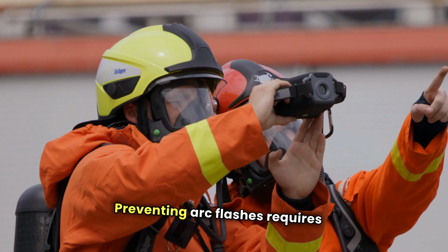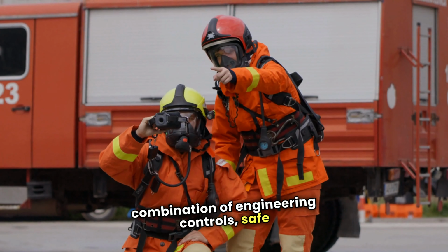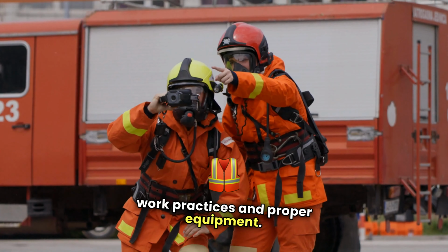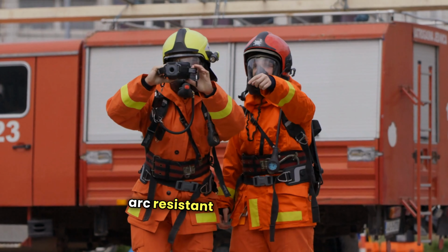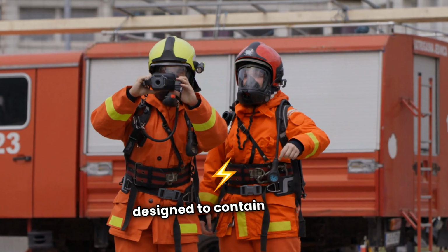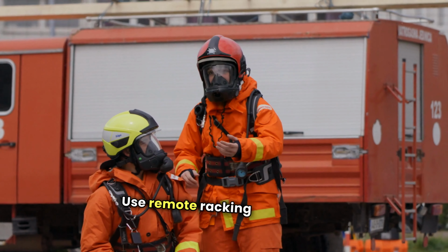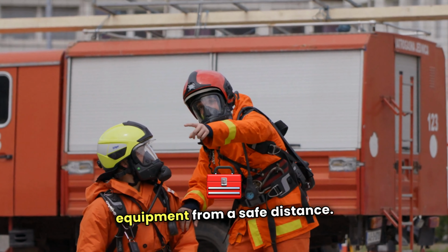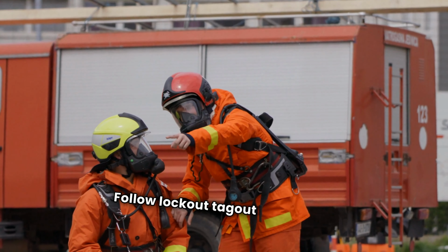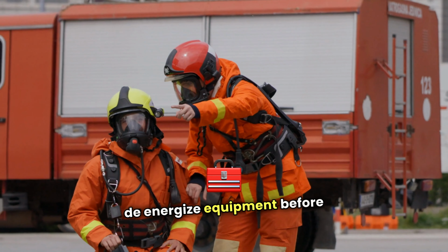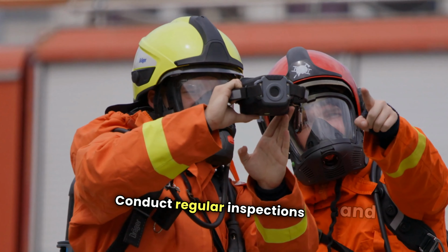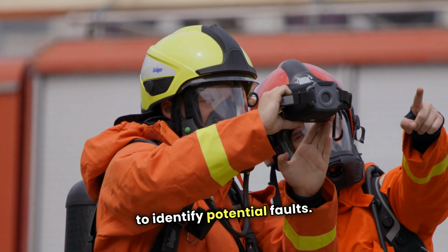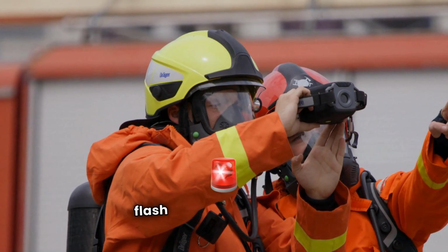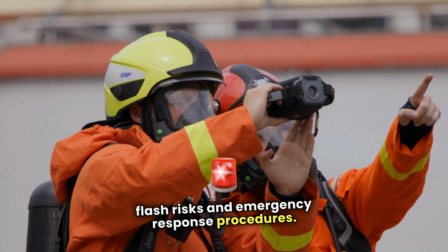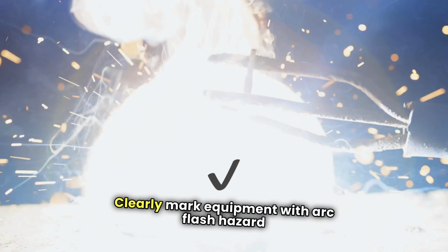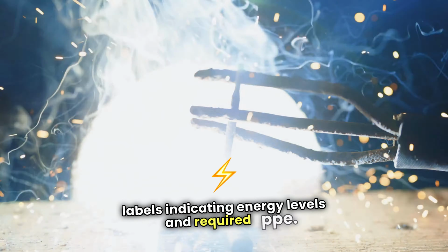Preventing arc flashes requires a combination of engineering controls, safe work practices, and proper equipment. Here's what you need to do: install arc-resistant switchgear and circuit breakers designed to contain energy releases. Use remote racking systems to operate equipment from a safe distance. Follow lockout/tagout (LOTO) procedures to de-energize equipment before maintenance. Conduct regular inspections and maintenance to identify potential faults. Ensure all personnel are trained on arc flash risks and emergency response procedures. Clearly mark equipment with arc flash hazard labels indicating energy levels and required PPE.